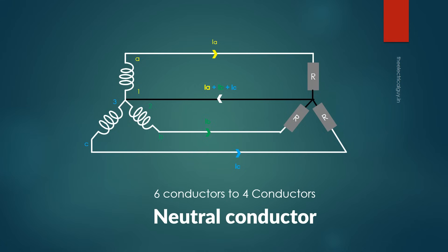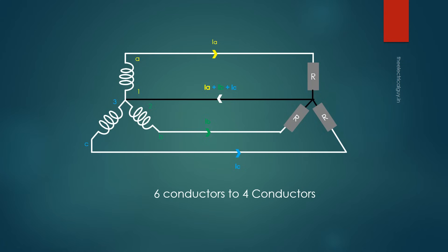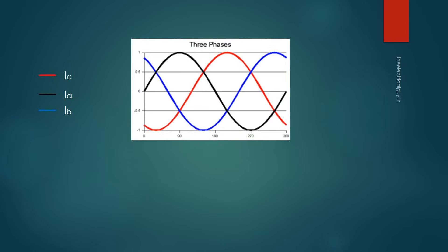The neutral conductor carries the sum of three currents: Ia + Ib + Ic. Many people think the neutral conductor must be three times the size of the other conductors, since it carries the sum of all three return currents. But the currents of the three phases are out of phase by 120 degrees from each other. If we draw a waveform for these currents, you will find that the sum of return currents is zero at every instance.